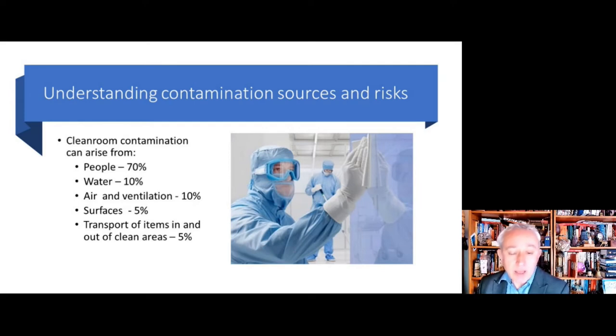There's also air, which is another vector. Microorganisms don't grow in air, but they're easily transported in air currents, or if they're on larger particles, there's the gravitational settling effect. Then we have a degree of surface items. This could be naturally contaminated surfaces or the act of transferring items in and out of the clean room. That figure can be much higher if we have weak controls around the whole transfer disinfection process.